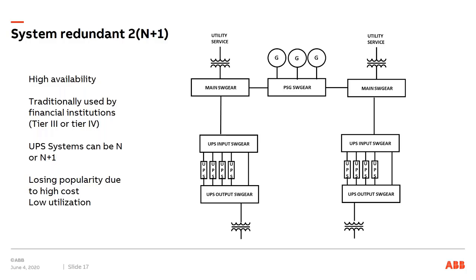And in the drawing here, you can look at the center, the power down the line, as an A bus, and the other one as a B side. Both are feeding the same load. So there's redundancy on UPSs on the A side and the B side. Practically anything can go wrong on both sides, and it's not going to affect the power to the load. There will be some way of getting power to the load from the B side or from a bypass. They will typically be more detailed or complicated than this single line.